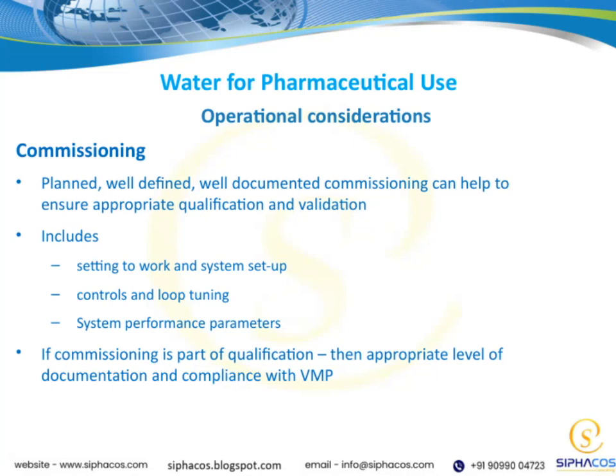Let's talk about commissioning. A planned, well-defined, and well-documented process is essential to ensure proper qualification and validation. This means that every step, from setting the system to work to tuning controls and loops, is carefully documented and executed. It also includes defining system performance parameters, so we know what to expect and can verify that everything is operating correctly. If commissioning is part of the qualification process, it's important to have the appropriate level of documentation to demonstrate compliance with Good Manufacturing Practices, or GMP.